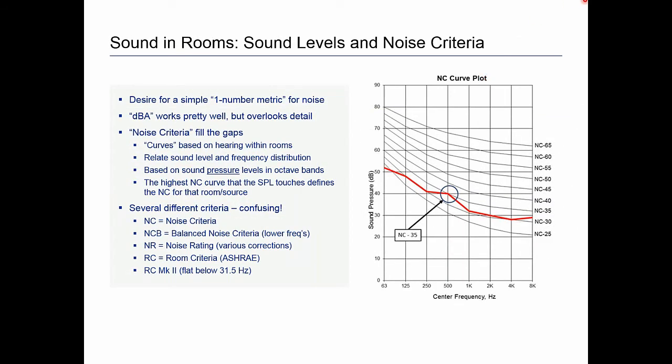There are lots of different ways to describe sound in rooms, and several are most common in HVAC work. Often there's a desire for a very simple one-number metric. dBA — a sound level in dBA in a room — is a pretty good descriptor. It works relatively well, correlated to how annoyed people will be: lower levels mean less annoyance, higher levels mean more annoyance. But dBA doesn't really describe the timbre or quality of the noise, or its frequency spectrum content.